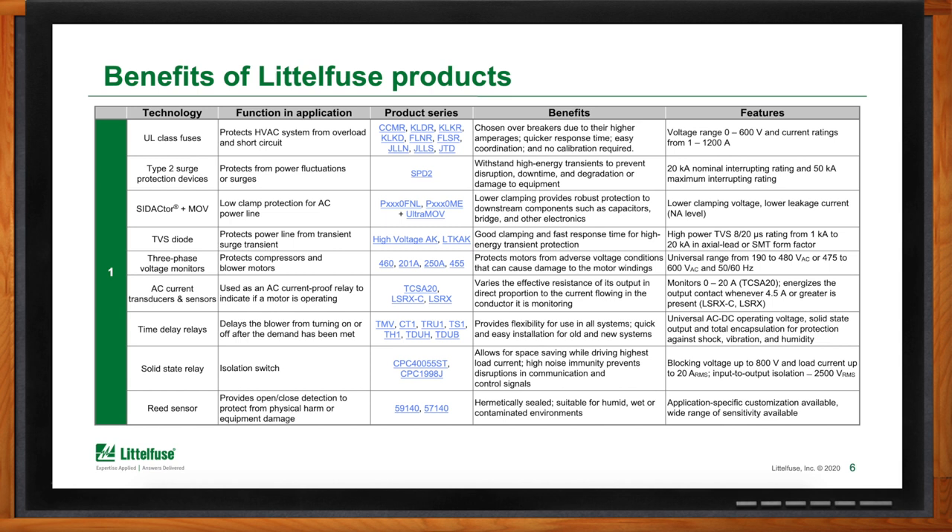Next, we have our SIDACtor Plus MOV protection. The SIDACtor and MOV combination safely clamps system voltages so as not to damage smaller components such as capacitors, transformers, and other small electronics. This unique combination provides very high surge current capability with an extremely fast response time and very low leakage current, translating to increased reliability and robustness of protection compared to competing technologies like a GDT (gas discharge tube). Next, in terms of AC line protection, we have our AK series high-voltage TVS diodes, typically found on the secondary side of the transformer for clamping the AC lines to protect downstream components. Our AK series offers good clamping and fast response time, available in both axial leaded and SMT form factors.